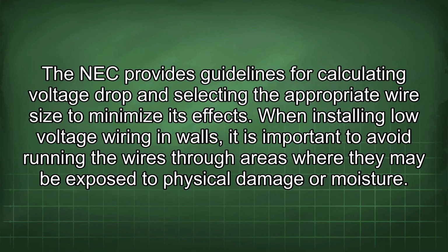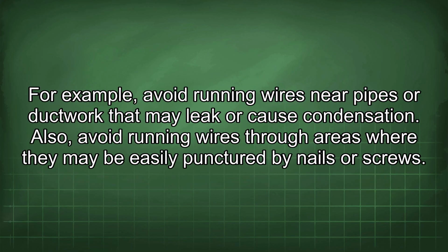its effects. When installing low-voltage wiring in walls, it is important to avoid running the wires through areas where they may be exposed to physical damage or moisture. For example, avoid running wires near pipes or ductwork that may leak or cause condensation. Also, avoid running wires through areas where they may be easily punctured by nails or screws.